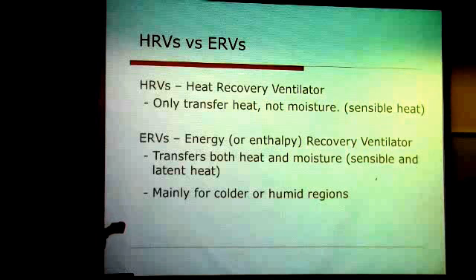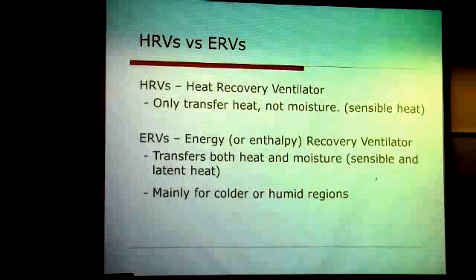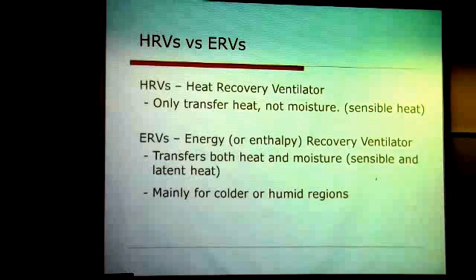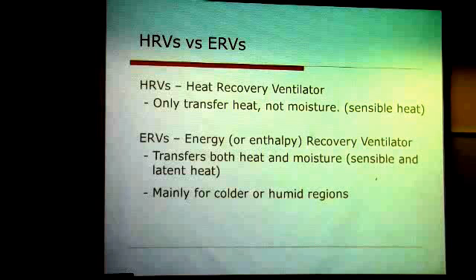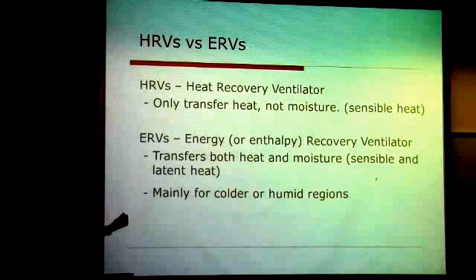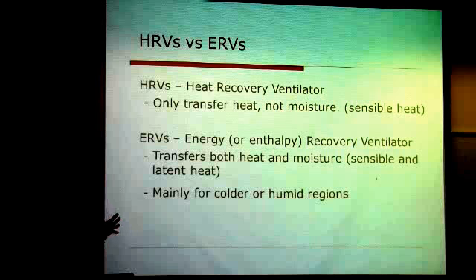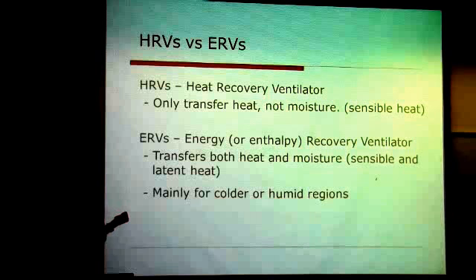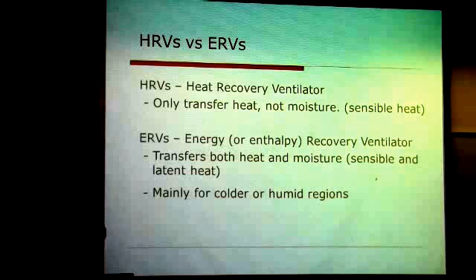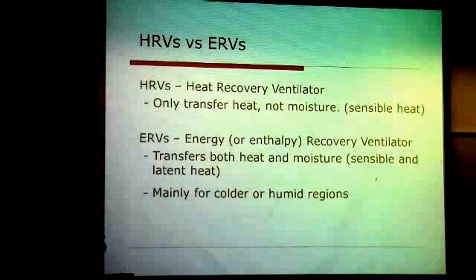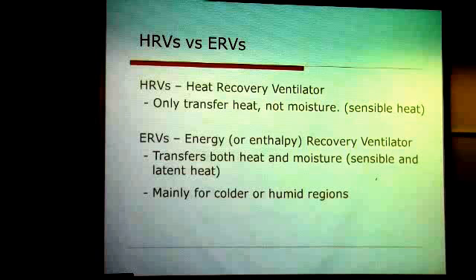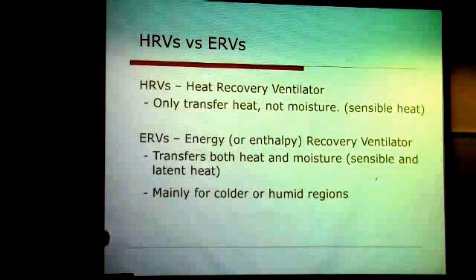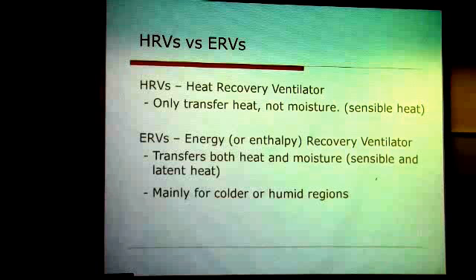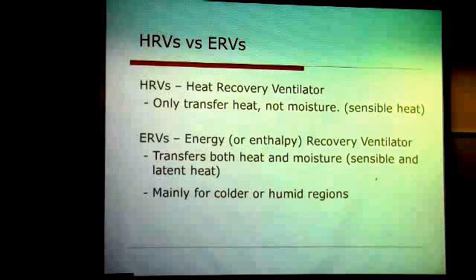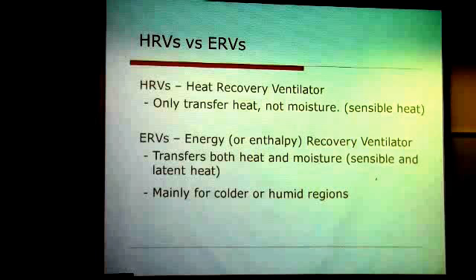When I first started, I thought, most of the time you talk about really cold, dry air, and when you heat it up, it becomes even drier because cold air holds less moisture, relative to the relative humidity. So you would think Alaska would need an ERV because it wants to keep the moisture inside the house, but they're finding they're building so tight up there that they're using HRVs, because they have more of a moisture buildup problem inside the house than a problem with dry air getting in. So they're using HRVs in Alaska. So ERVs are mostly just East Coast, Northeast, and places where it's hot and humid.